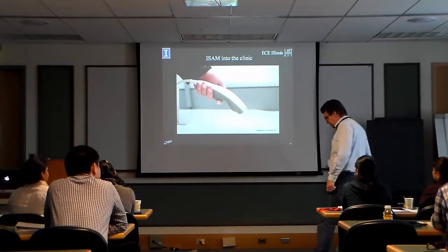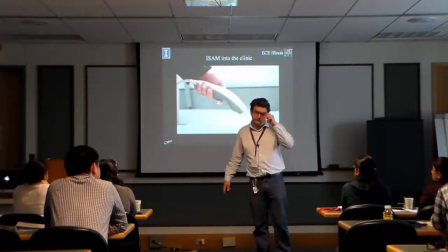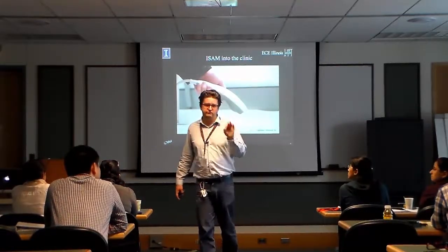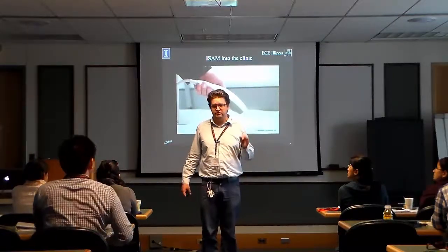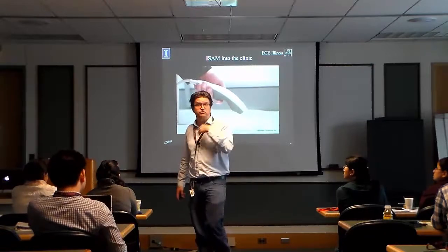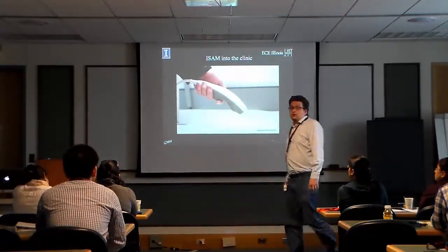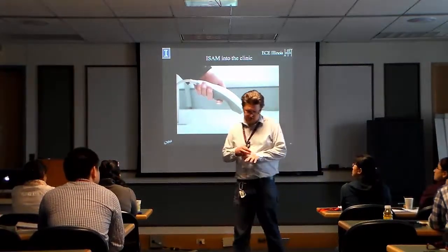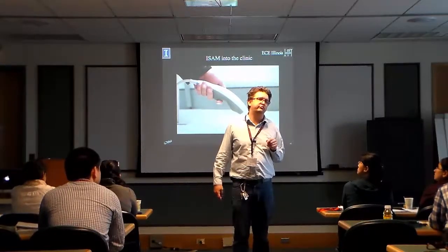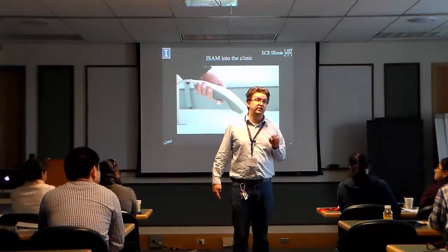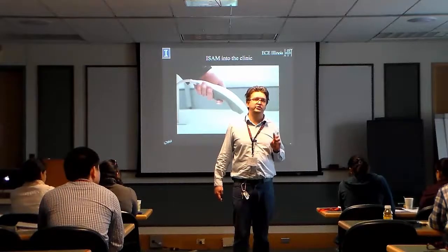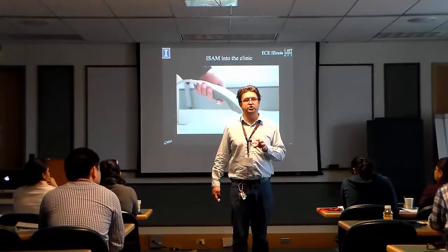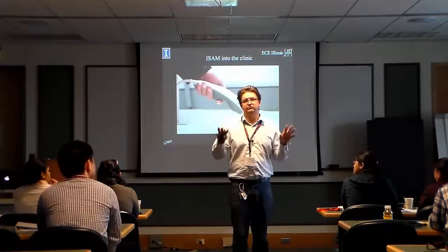The other hardware you need, in some sense, there's a hardware requirement that you require phase-stable data, which in the bad old days was a real challenge, and we had to do all kinds of funky tricks with the hardware. Now the lasers are getting fast enough that it almost comes for free. Basically, if you make a really fast measurement, your phase remains stable. So we're dealing with an A scan rate in the 50 to 100 kilohertz range. That's fast. And there you kind of get the phase stability almost for free. You have to work a little bit, but not very hard. In the bad old days, we were working at sort of the 10 kilohertz regime, and there it's a mess, and you have to have a reference surface and correct the data later.